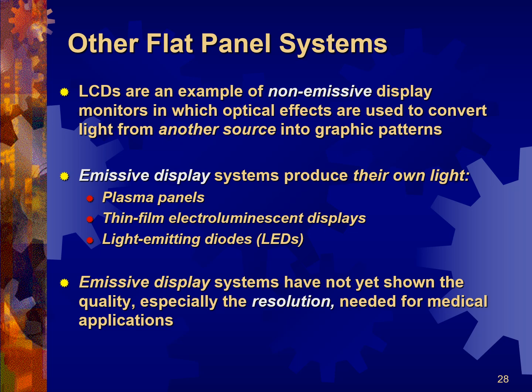Those are emissive displays. LCD is a non-emissive display. I would even call it a passive display because it requires an external light source to work. That light source is housed behind the monitor. Emissive display systems like plasma have not shown the quality for medical applications, so we can achieve a higher resolution with an LCD monitor than with any of the emissive display technologies.